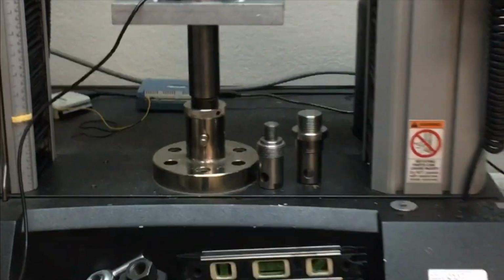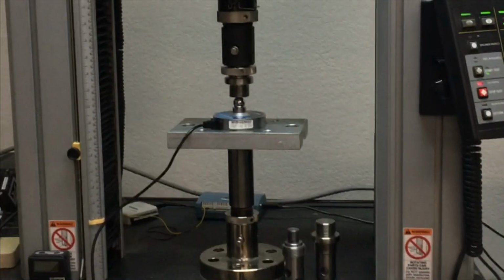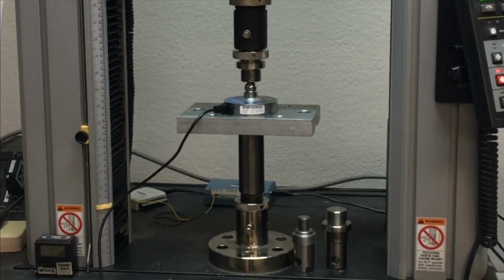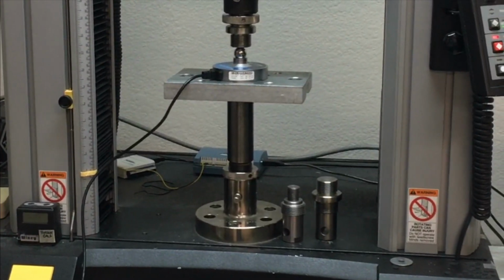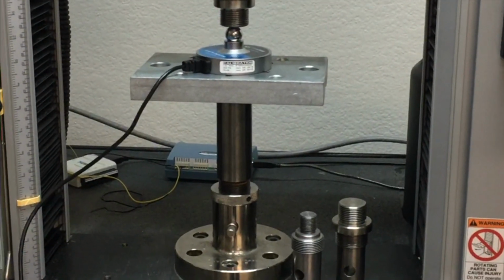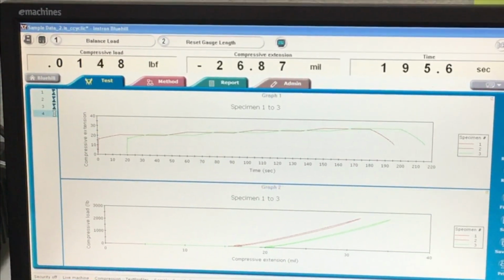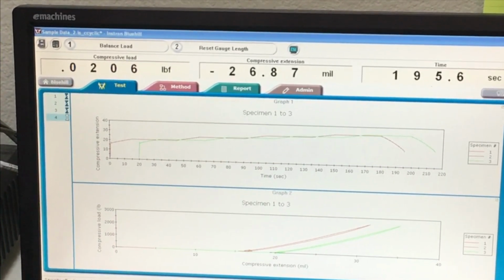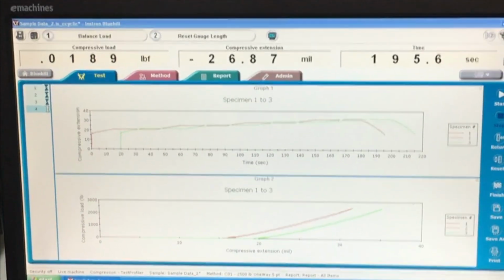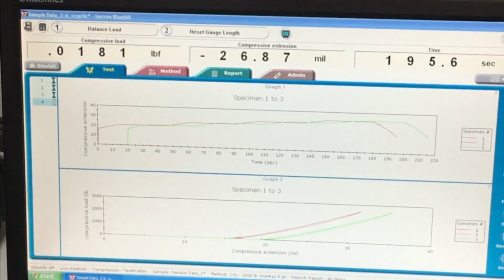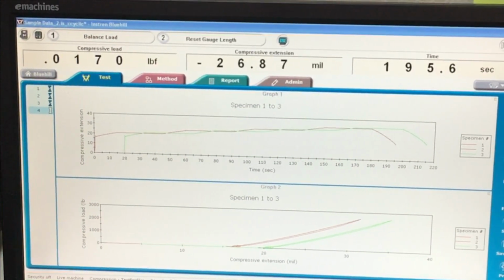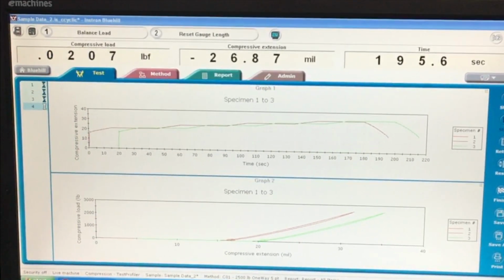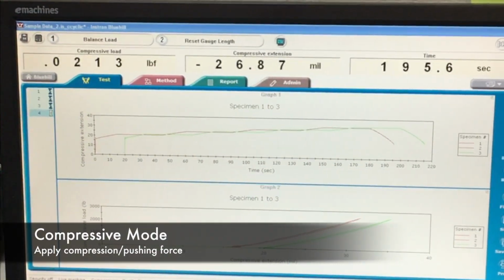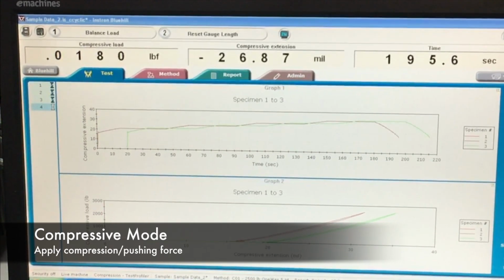Now we're going to use the Instron that we have, the machine that we use to apply known loads. This machine is calibrated to NIST standards and is traceable all the way back to NIST standards. So we're going to use this machine and our Blue Hill software to apply the loads. And we have a preset 2,500 pound profile set up to apply the load on this 2,500 pound load cell.